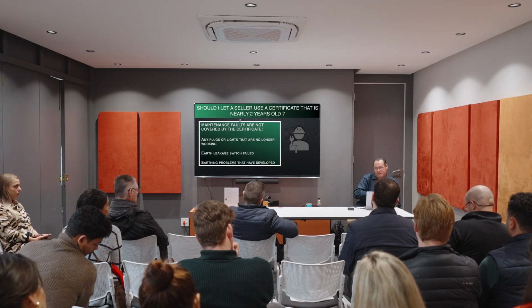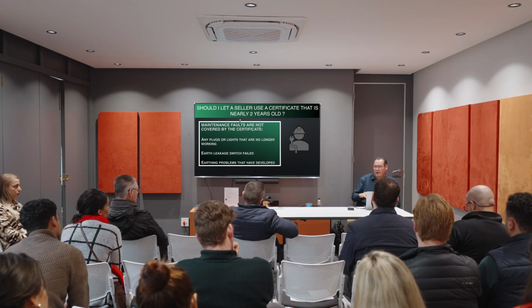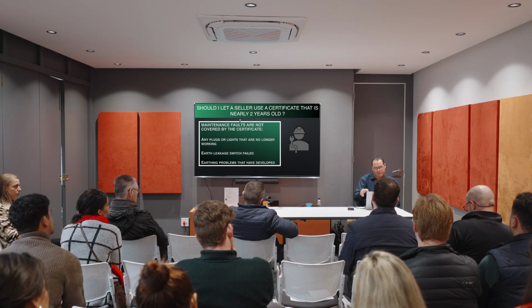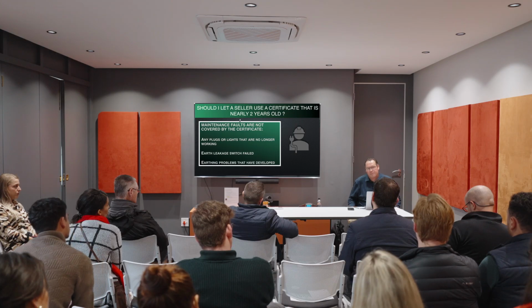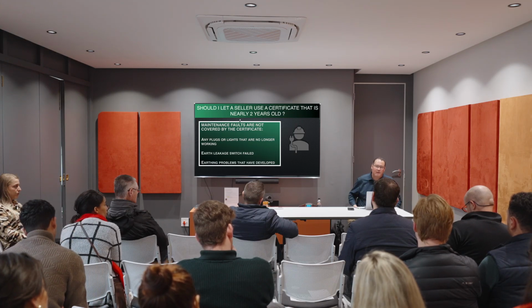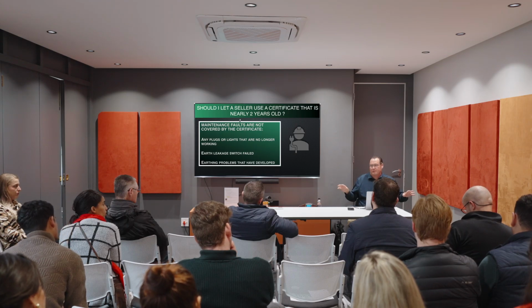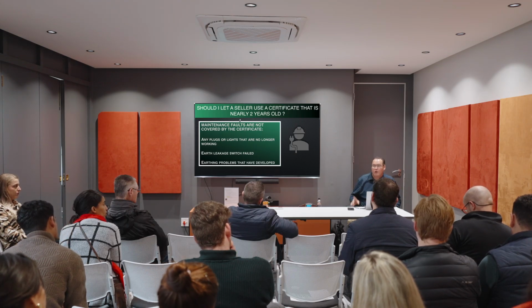Everything's bolted together, lock nuts, everything's bolted, and that is your earth. They are saying you can no longer use metal conduit for earthing, and they are correct for a new installation - you can't go and install metal conduit as an earth now. But if the house is 60 years old and that's the earthing system, you can still pass it. We've seen quotes for a little house out in North Pine - 26,000 Rand to rewire all the lights and plugs because there's supposedly no earth wire.